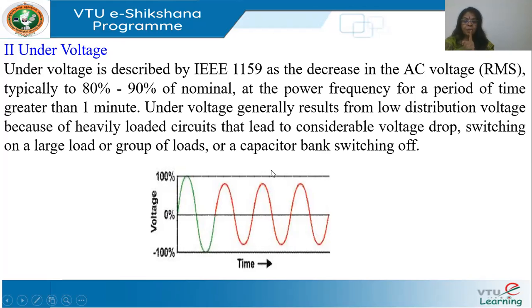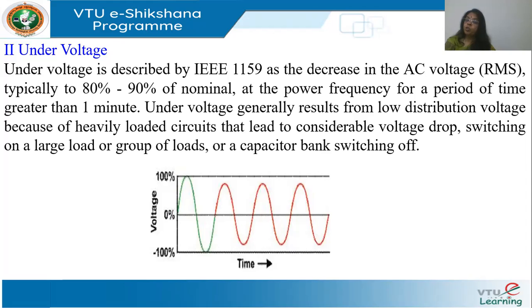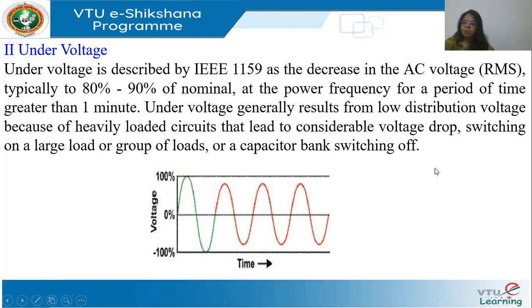Switching off a capacitor can also cause under voltage, since capacitors are used to improve the voltage profile. For example, capacitors switched off during light load in the morning may not be switched back on as the load picks up, resulting in under voltage. These are all steady-state phenomena described in terms of RMS values, not amplitude.